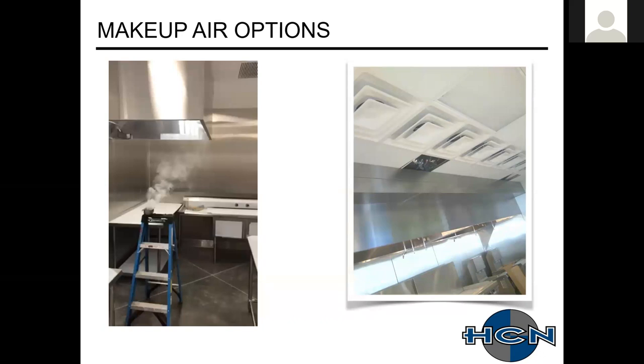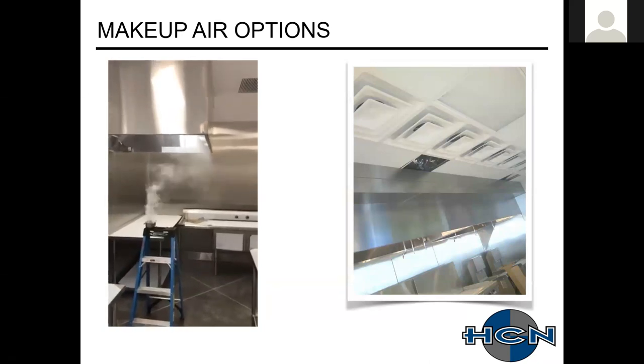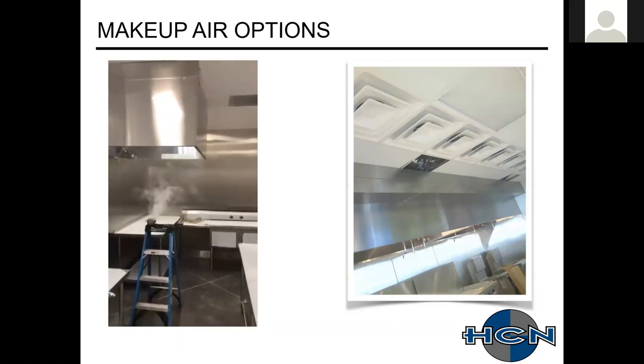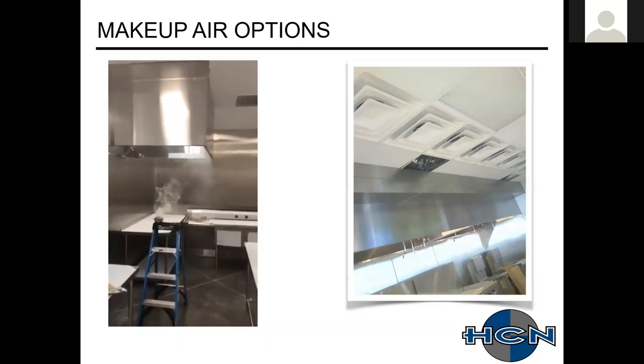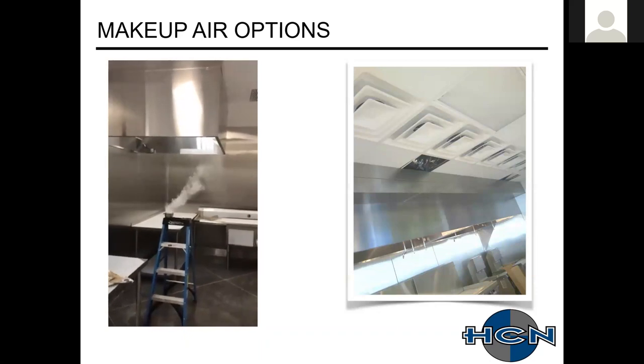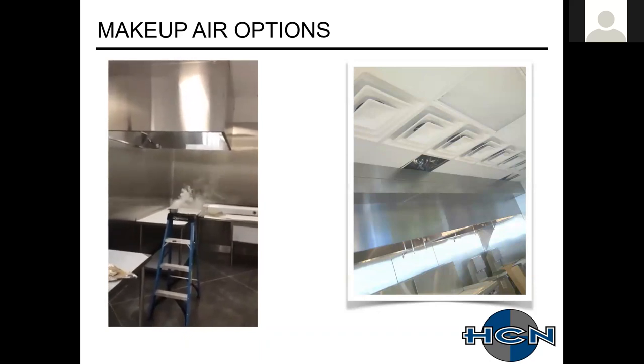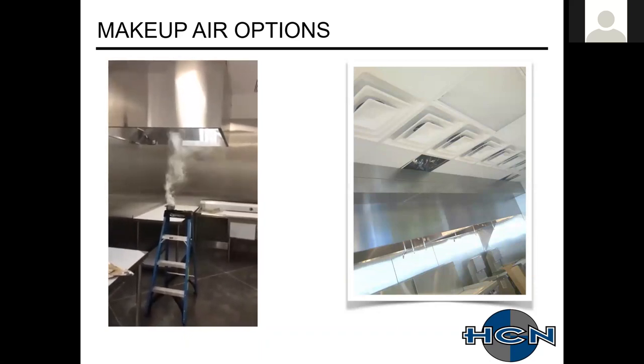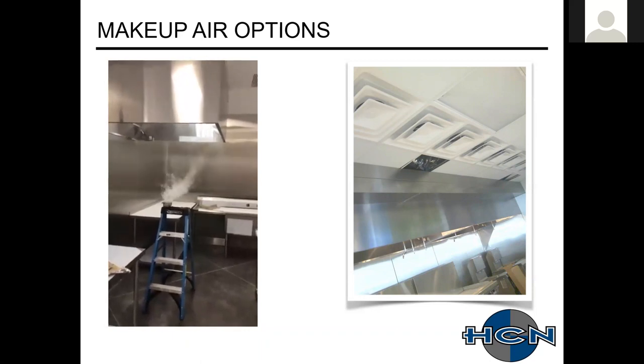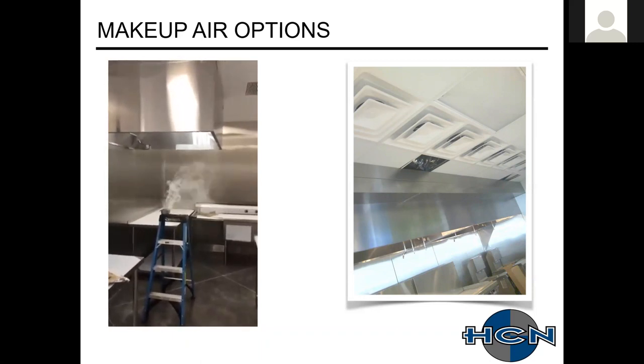I have a video here of a hood. There's no equipment in there, but I think it's a one-way slotted diffuser right in front of it. And this is just from a smoke bomb. And you can see it pulling out the effluent. And that's load going right into your space that your rooftop units or any of your equipment would have to overcome.